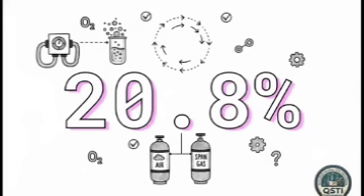All right, as we move into the configuration prep, our very first task is telling the machine exactly what span gas concentration it should expect. And the magic number here? It's 20.8%. This is the default factory setting for the O2 span concentration value. And for good reason, it really closely approximates the actual O2 content of the ambient air we breathe. We absolutely need the software's expectations to perfectly match the physical gas we're feeding it.